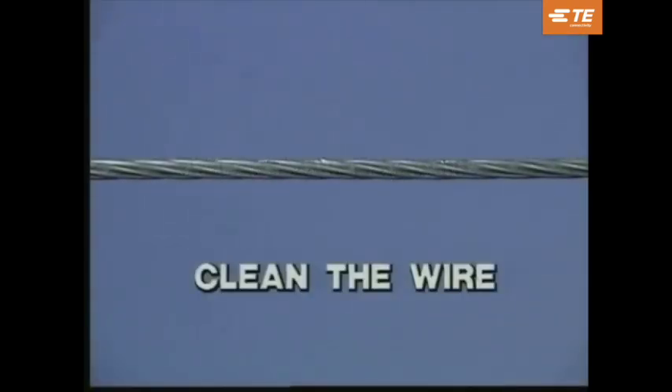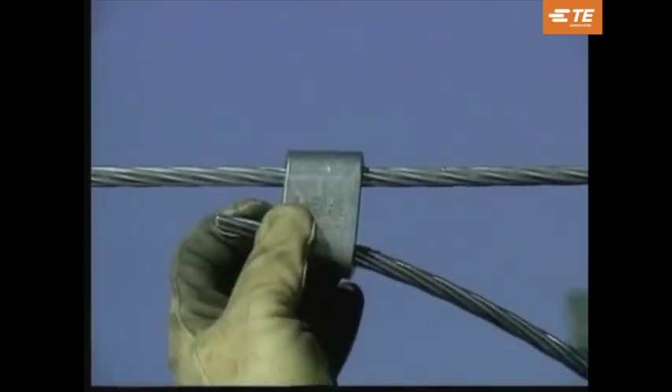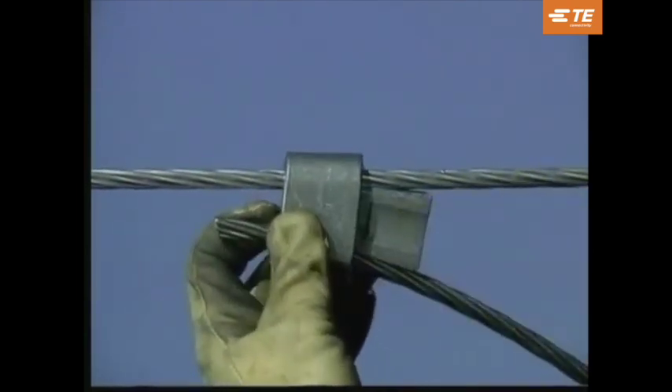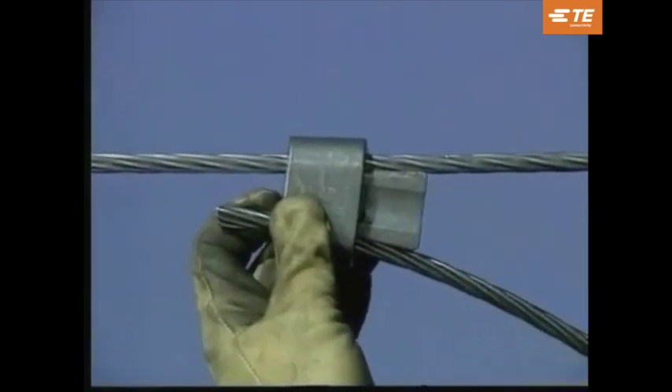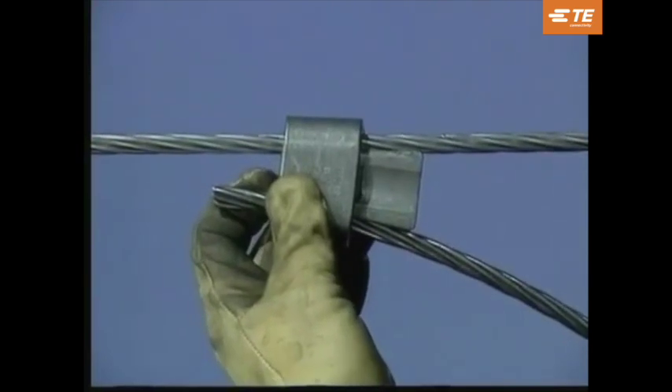Before installing an AMPACT tap, thoroughly clean the wires by an approved cleaning method. After the wire is clean, place the tap wire into the bottom groove of the C-member. Then place the C-member on the through wire — this method prevents placing your body in a possible series path. The back of the C-member should now be facing the installer. Insert the wedge with the large wire groove, identified by a letter or number, aligned with the large wire. Finger tighten and tap the wedge into the C-member to seat it. The tap should now be self-supporting.